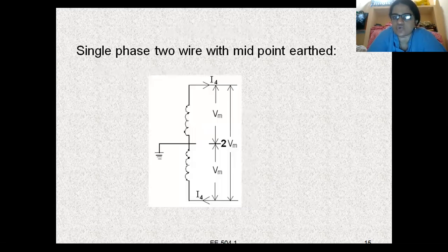Coming to single phase two-wire system with midpoint earthed. Again this is single phase, meaning only one wire, but we are trying to use two wires. Single phase two-wire with midpoint earth means we are separating that single winding into two parts. Again we have two wires, one from top and one from bottom, with midpoint earthed, and the middle point of this wire is earthed. So this is called single phase two-wire with midpoint earth, and the total voltage here is also 2 Vm.